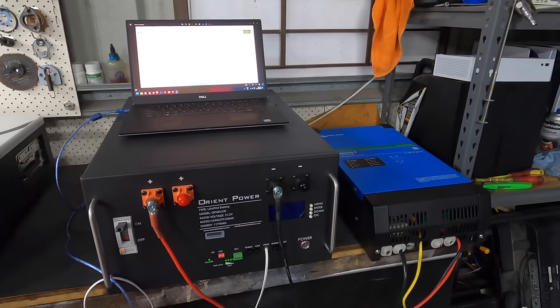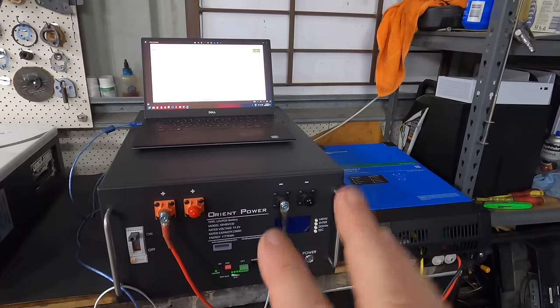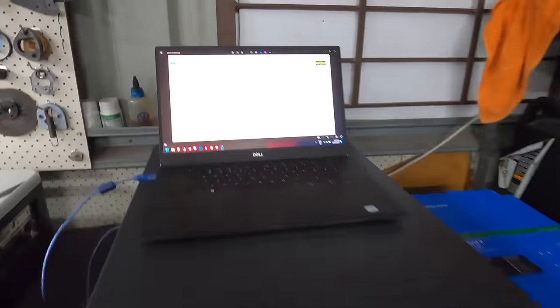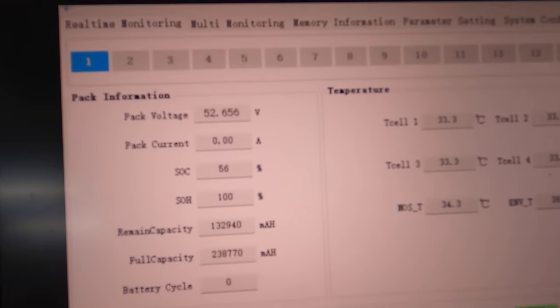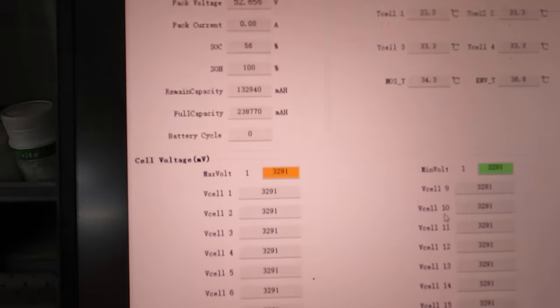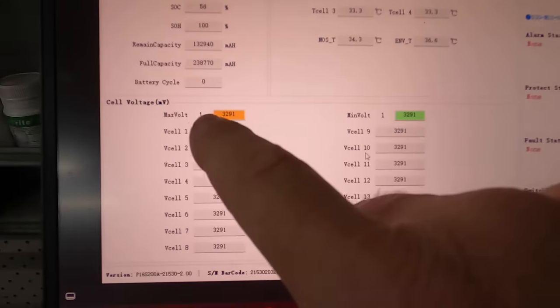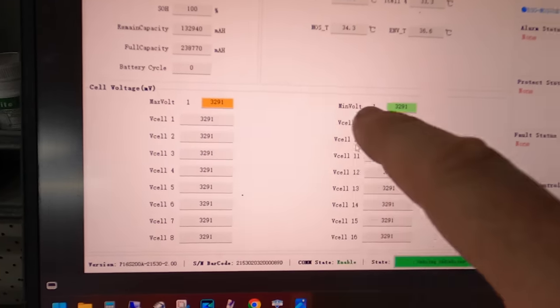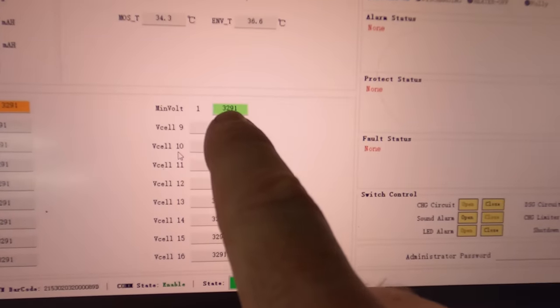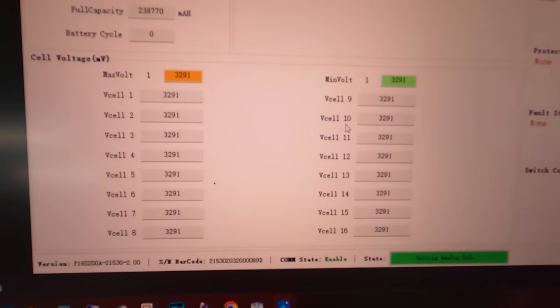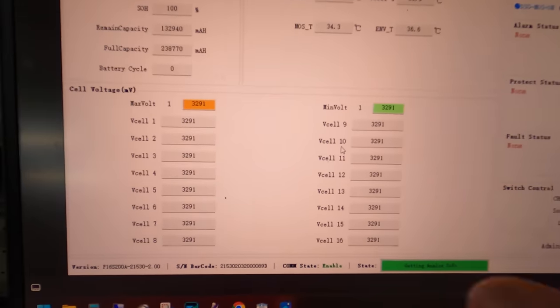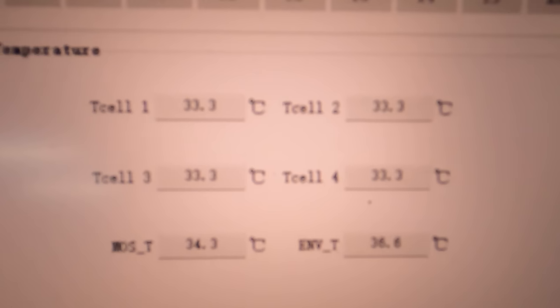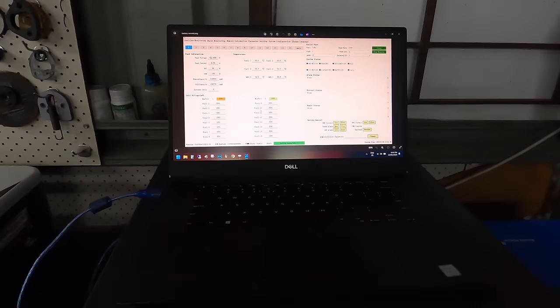Set up a little bit of a test rig here. We've got the Multiplus to actually charge the battery up. When the battery arrived it only had 56 percent state of charge and the voltage was 52.656 volts. Down below here we've got the minimum was 3.29 volts and 3.29 again, so it was perfectly balanced according to this software when we got the battery. The battery temperature was actually 33 degrees, which was nowhere near as hot as the rest of my workshop.